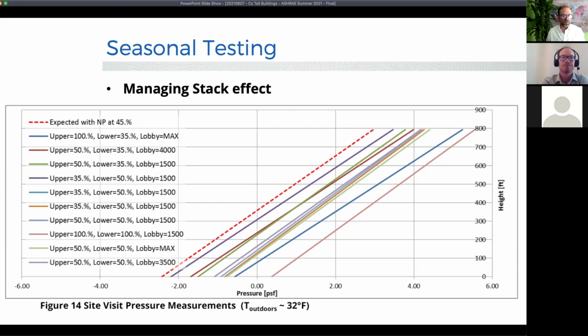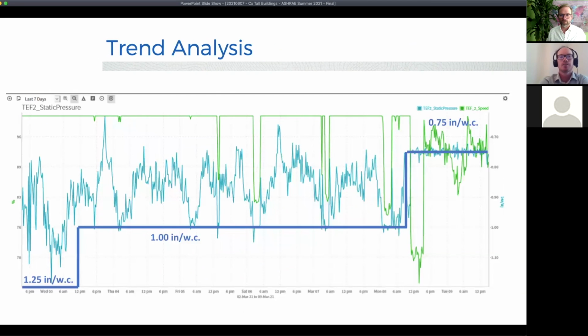So this is an example of different tests we ran with the systems, where we could see the neutral plane of the building shift with different control strategies. This was a great example of how we can run things. We do this a lot in our commissioning procedures, trying to run different scenarios to understand and map out the whole program. And I'd like to note on the point that Ben made about set points, right?